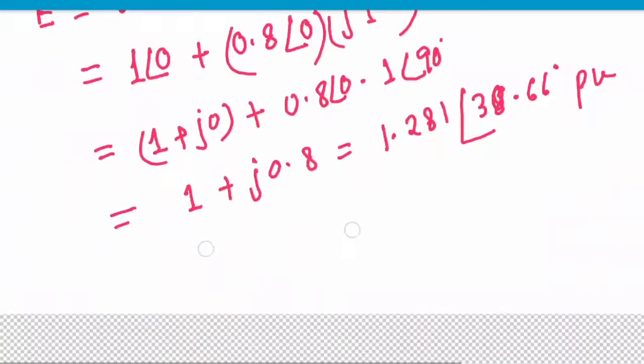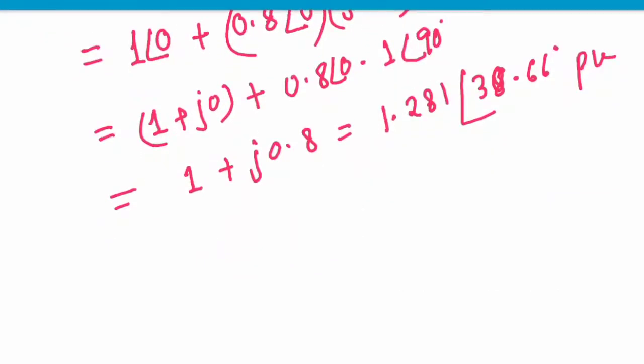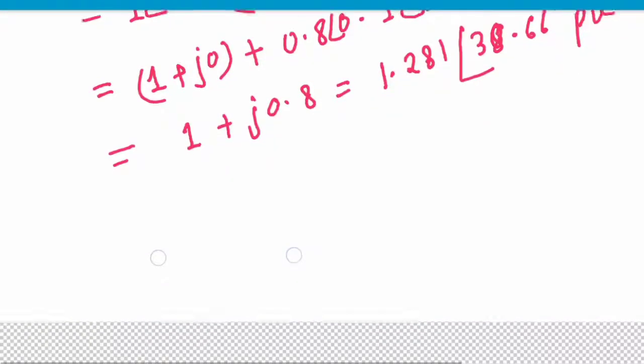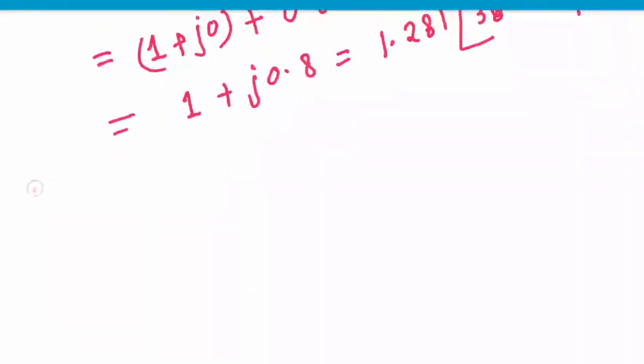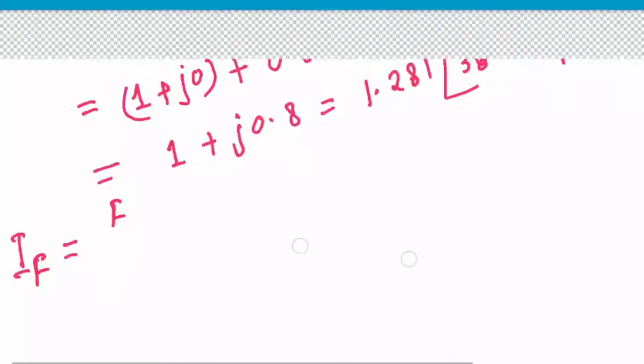E is 1.281 per unit. When a symmetrical short circuit fault occurs, the sub-transient reactance Xd double prime comes into picture. Xd double prime is the sub-transient direct axis synchronous reactance. The fault current will be determined by this reactance.